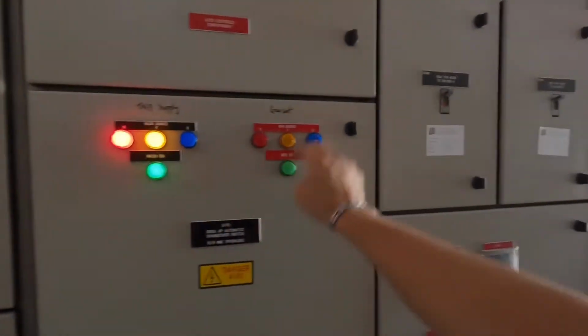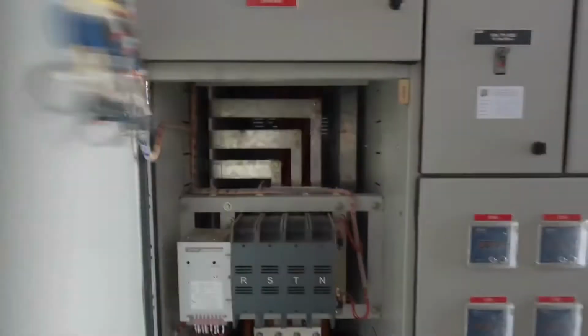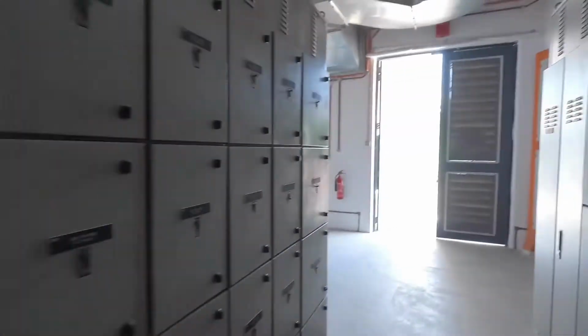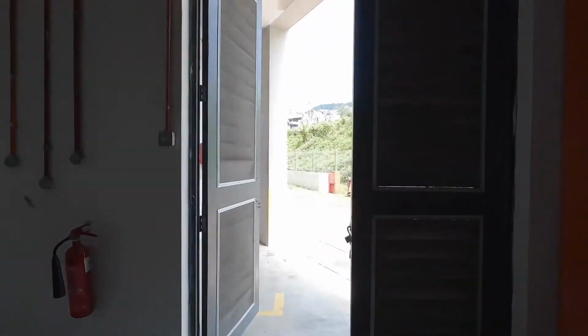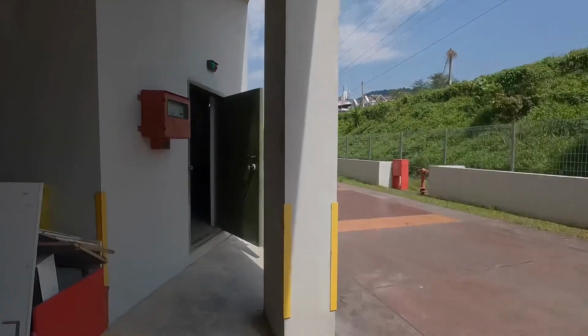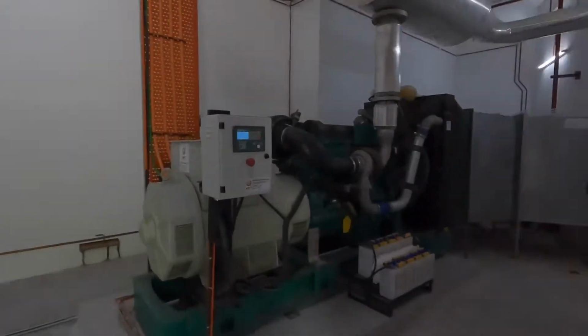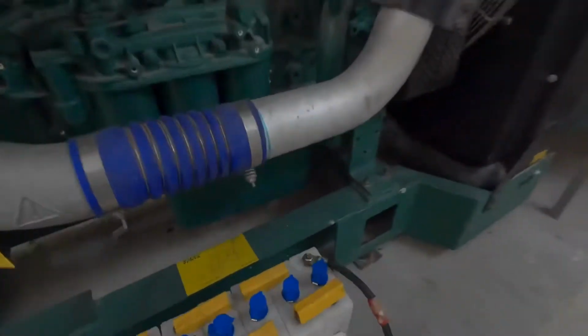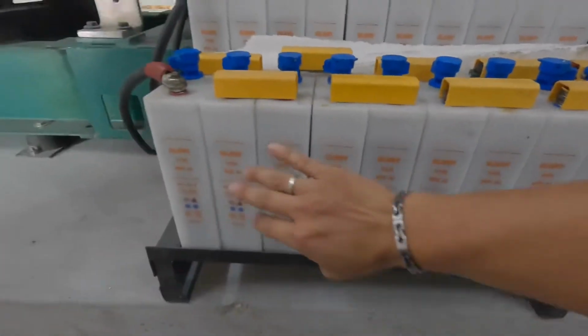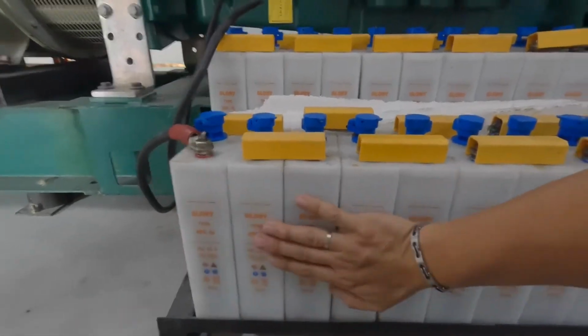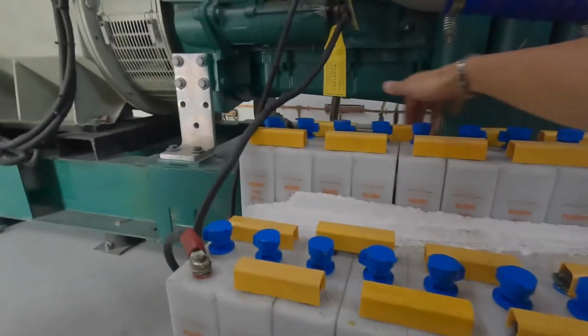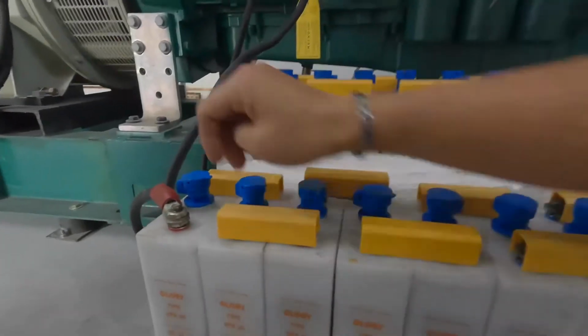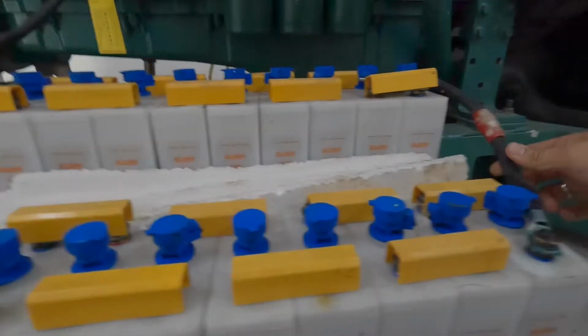Okay, here we have the ATS panel. Alright, this is the ATS panel, and this is the ATS, and the control panel is here. Alright, now before we test run the genset, let us go to the genset room and check the parameters before we test run the genset. Okay, here we have the genset. This is a nickel-cad battery. Currently, I'm just checking whether any overload charging conditions happen or not. Okay, no issue, but the cable has some oxidation here.